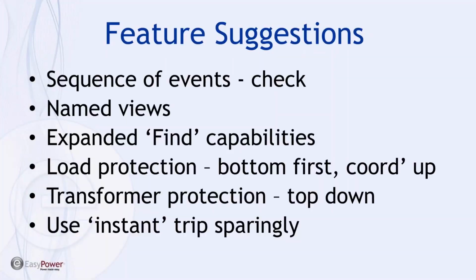Pretty much for load protection, you want to start at the load and then coordinate as you work your way up, which is pretty much what I was trying to do here. On transformer protection, you need to start at the top and make sure of your primary protection. In fact, that's the one place when you know the maximum loading on a transformer, that's a convenient place to use instantaneous trip in a relay, because you don't want any current above that, which is going to be an internal fault. So again, use it sparingly, because using it too much will contradict coordination efficiency.